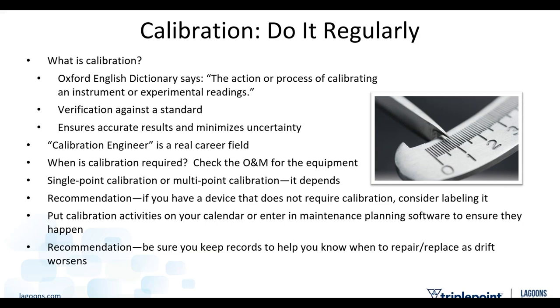I do have a recommendation here: if you have a device that does not require calibration, stick a label on it. That way, if someone is walking around doing an inspection of your plant and they want to know when the last time something was calibrated, you don't have to tell them that you don't have to calibrate that blower. You just point to the sign. Very easy. And again, put it on the calendar. Enter it in your maintenance planning software if you're using a platform for that. And that's a great way to make sure that they happen.